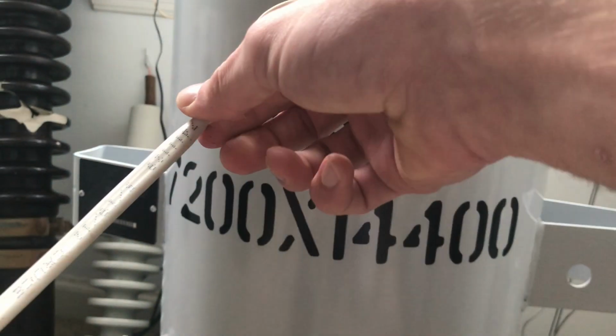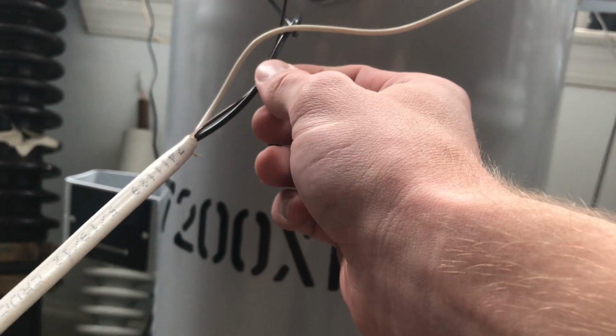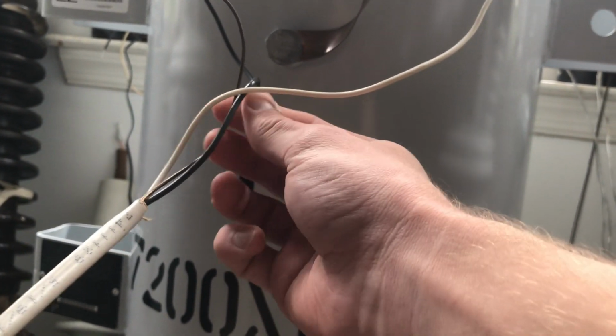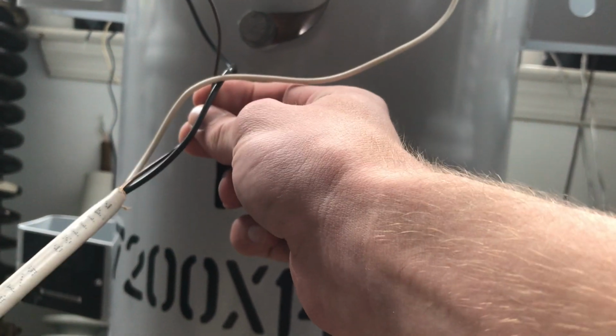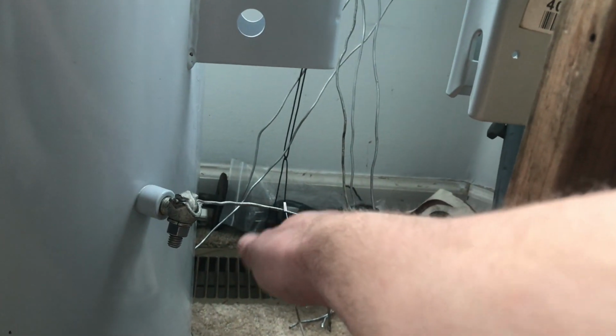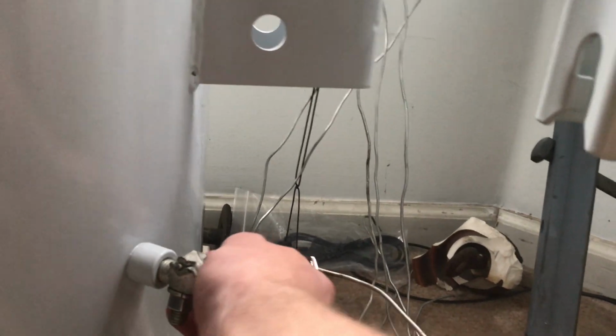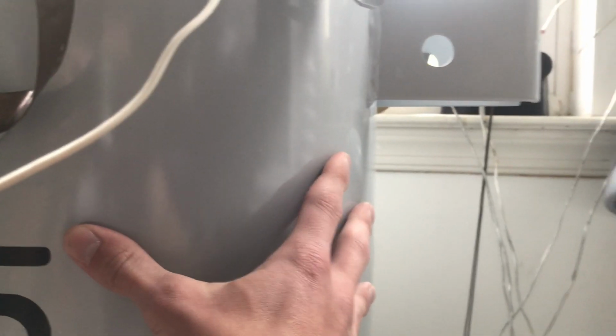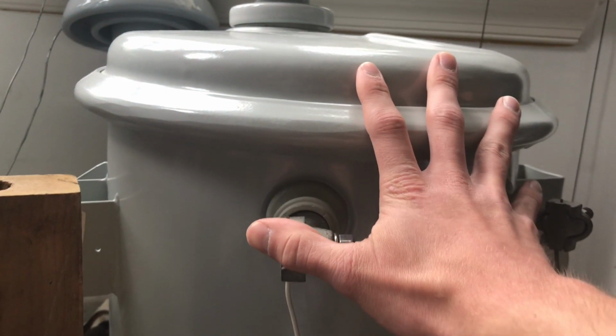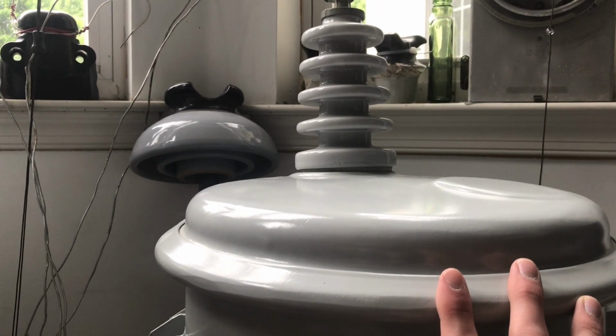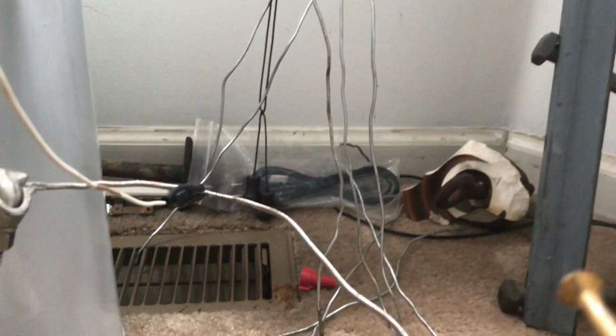That's why this is 14/2 wire, because the number of wires that is counted are current carrying. So you have a current carrying hot wire and a current carrying neutral wire. The ground does not carry current ever in a residential system. However, this wire here on the utility side always carries current on a single phase load. If this wire were to be cut and disconnect from the source, which is this transformer here, this whole transformer and everything attached to it would become live at 7,200 volts. And that's why it's always crucial that grounding is taken care of.